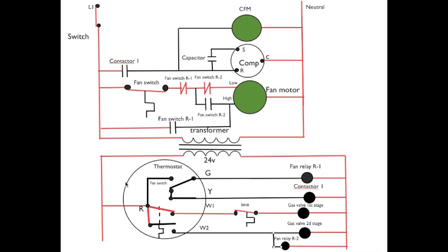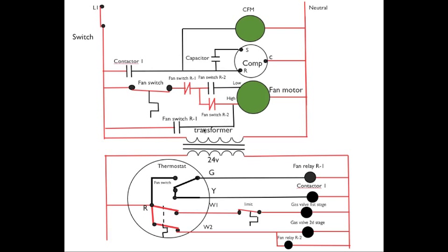Now you can see we have energized second stage. So the first stage is energized, fan switch is closed. The power has also come down through W2, energize the gas valve in second stage, and it's also energized fan relay R2, the coil of fan relay R2.